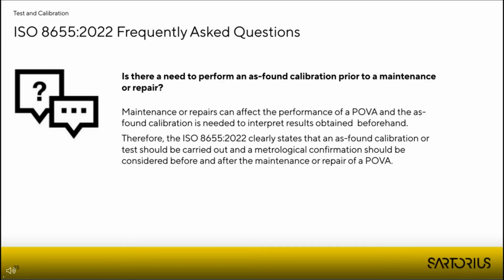And the second question: is there a need to perform an as found and as left calibration, so a calibration before maintenance or repair and a calibration after maintenance and repair? And also here the new ISO is very clear. As the maintenance or adjustment or repair can affect the performance of the pipette, a metrological confirmation should be considered before and after maintenance, adjustment, and repair.